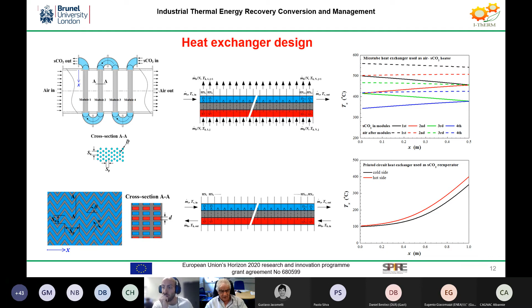This heat exchanger is placed in the duct of the process air heater, and then there's the printed circuit heat exchanger, developed and well established by Heatric, using 3D modeling of the heat exchangers, particularly to optimize the design of the microtube heat exchanger, but also different configurations of plates for the printed circuit heat exchanger. We've done a lot of modeling in this area, both 3D CFD and 1D CFD, used in the steady state and dynamic simulation of the system.